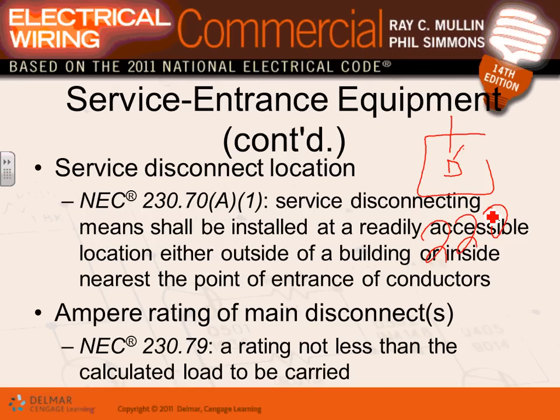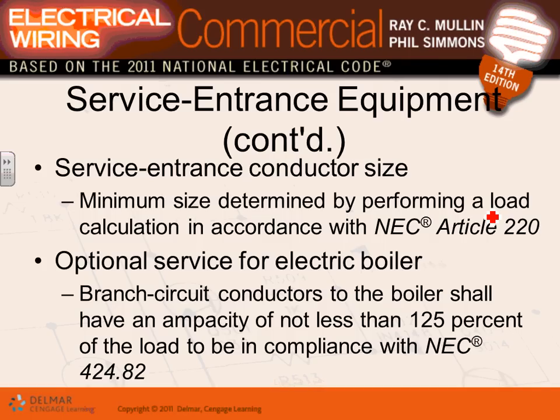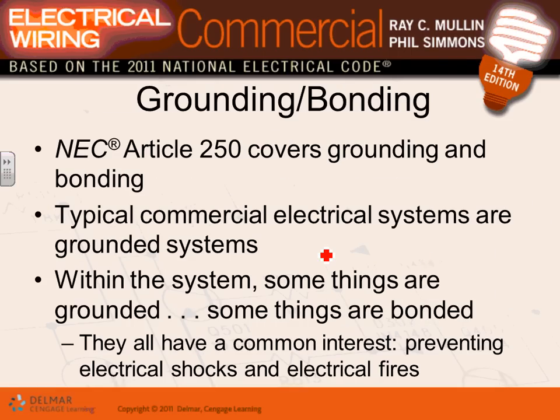Any comments about the disconnect? All this information, you've done it. You've done it for the residential project and the commercial project as well. Service entrance conductors, these are what you size with me for your load calculation. If you have a big boiler, they allow you to have a whole service just for the boiler, and you size it at 1.25 because it's a bigger load. Any comments? Any questions?